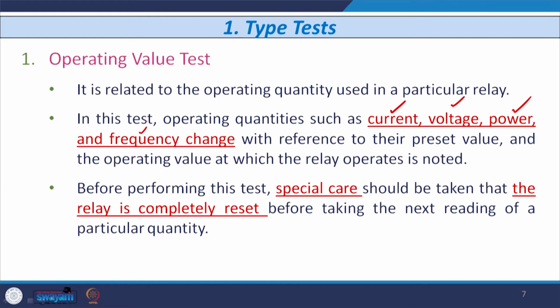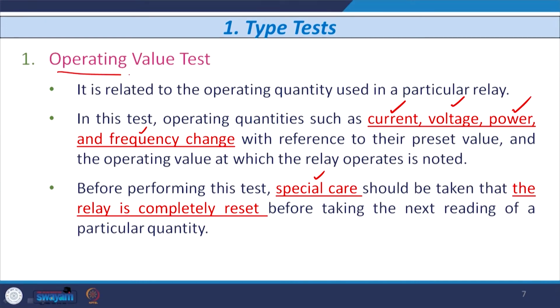The operating value at which the relay operates is to be noted down. Before performing this test, some special care is required. The relay should be completely reset before taking the next sample or next reading, otherwise you will have the wrong value, because once the relay starts operating, after that it will come back to its original position. If you start taking the next reading before it comes to the original position, the relay has performed only half the distance and you start again, so that will give a wrong reading. This is one care that is required when you perform the operating value test.